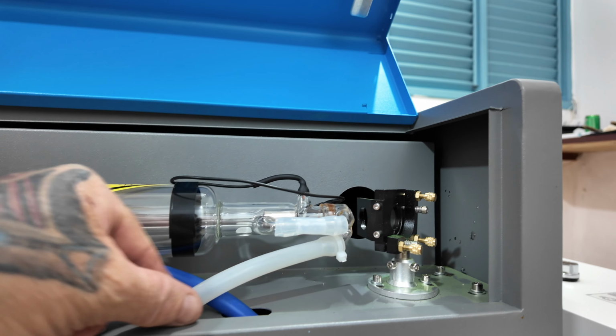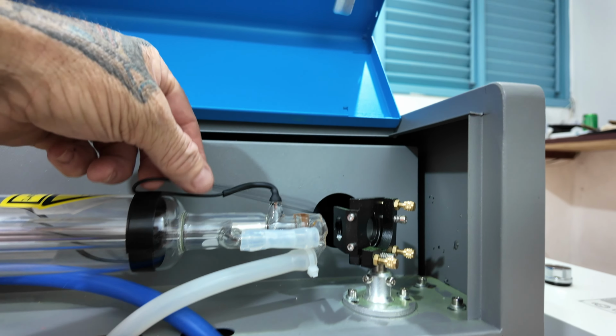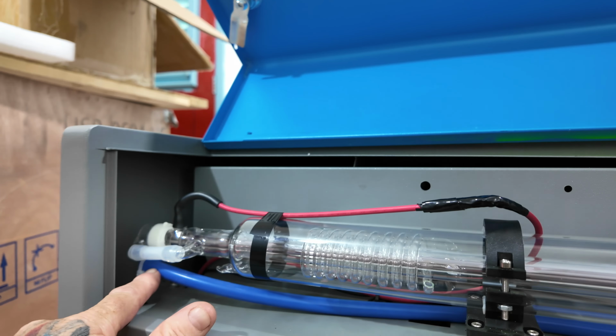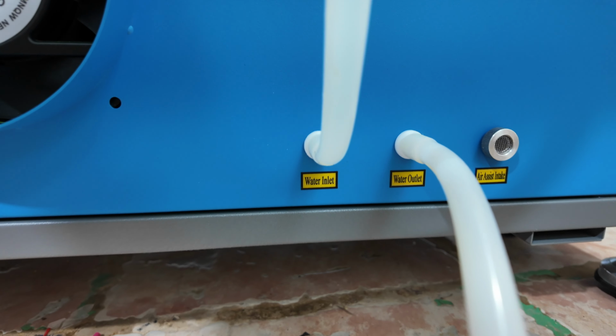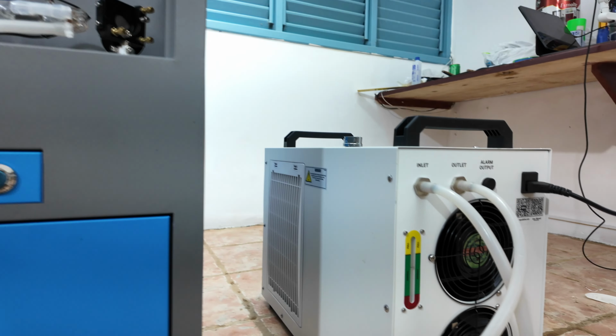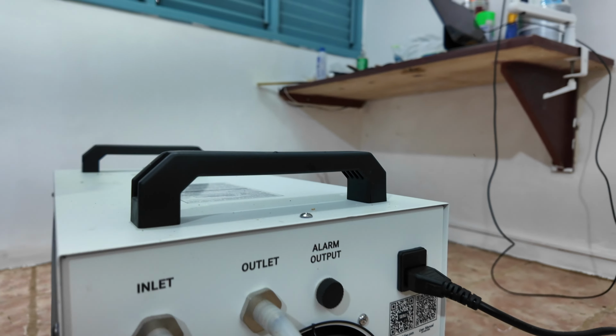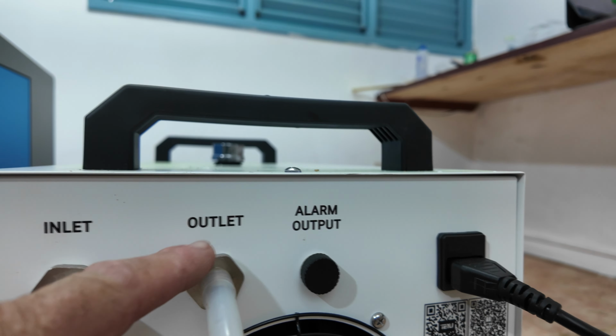We have the water hoses in, nothing's pinched. We have the wires connected. We have the high voltage wire, we have our line connected. And coming over here, we have the water inlet line. And that water inlet line comes all the way over to the chiller and goes to the outlet.